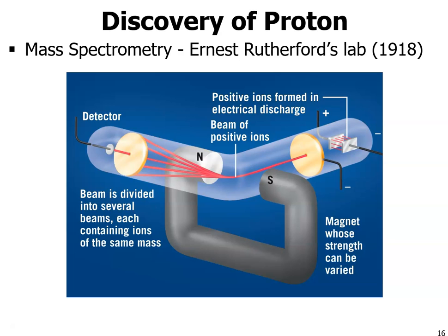They had a front-end compound which stripped electrons off a substance entering this area. Then we knock off those negatively charged electrons, and pass this through a negatively charged condenser that keeps the flow of ionized compound going through here. Its trajectory is changed by this magnet, with different magnetic powers applied, and then it hits a detector. And that detector tells us how much that thing weighs.